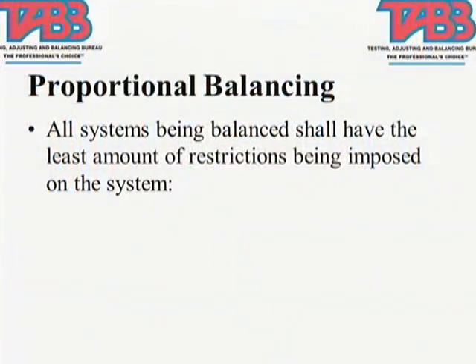Proportional balancing, and the importance of this and how this all ties together, is when we start talking energy efficiencies. It's when we say this: all systems being balanced shall have the least amount of restriction being imposed on the system. It's a lot to say in one sentence. And when we look at it and we go over it, we are saying all systems being balanced shall have the least amount of restrictions being imposed on the system, meaning we don't have too many dampers turned down. Associate it with punching yourself in the face. At one point, you start hurting yourself instead of helping yourself if you start having too many dampers or valves closed where the pump or the fan has to push against more resistance than what's needed. And with sequential balancing, that's usually what happens.